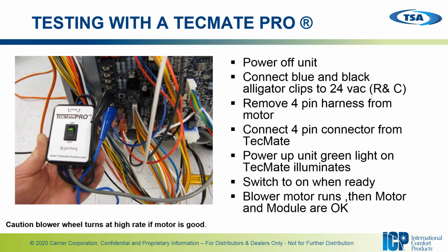All right, and to do so, just power off the unit. You're going to connect the blue and black clips to 24 volts, which would be R and C. Remove the 4-pin harness from the motor. Connect the 4-pin connector from the TecMate Pro.